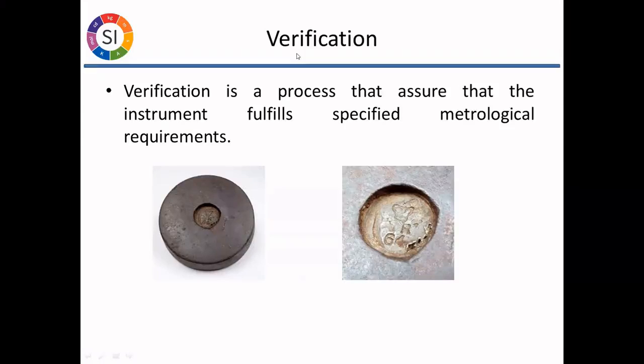Verification is another word that can be confused with calibration. Verification is a process that assures that the instrument fulfills specified metrological requirements. After the verification, if the instrument fulfills the required specification, then the instrument will be sealed in a way that the instrument can't be adjusted to give faulty indications. This photo shows the verification mark of a weight used for trade purposes. Here, a crown is there because it is a symbol for another country, but in Sri Lanka, a swan is used as a symbol.